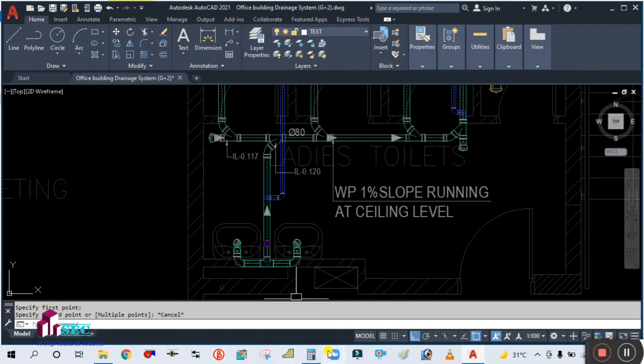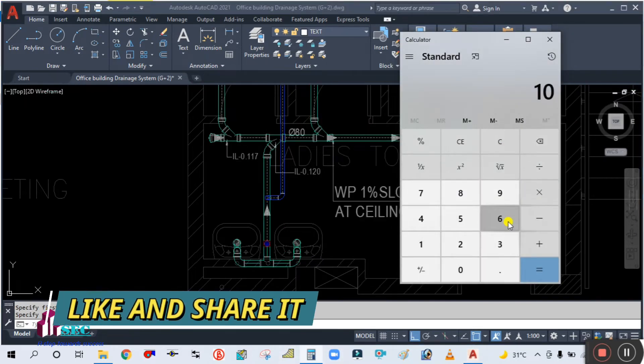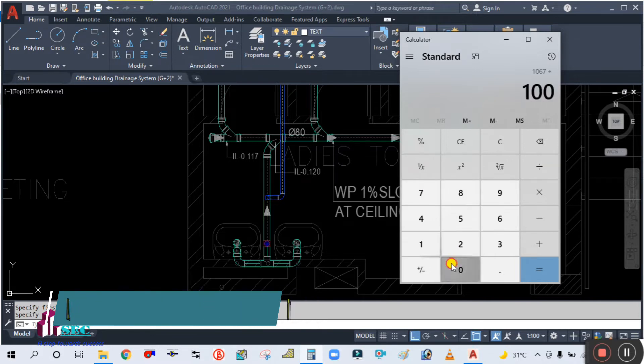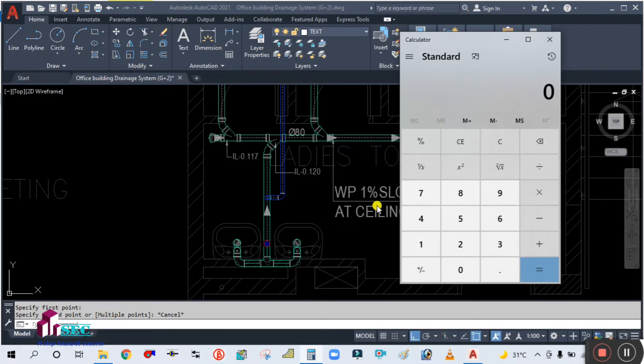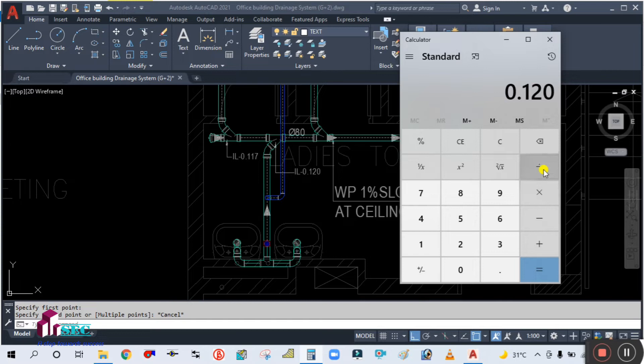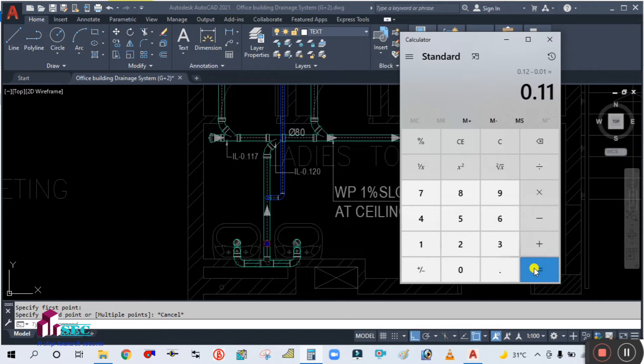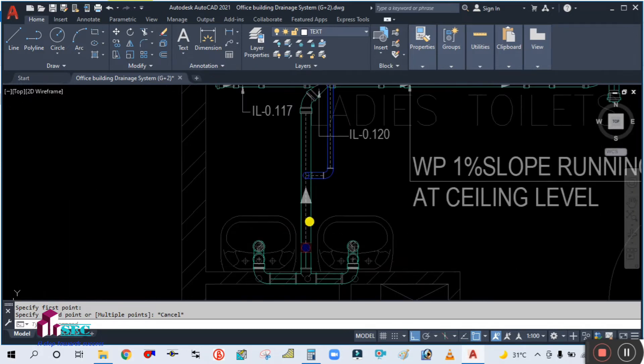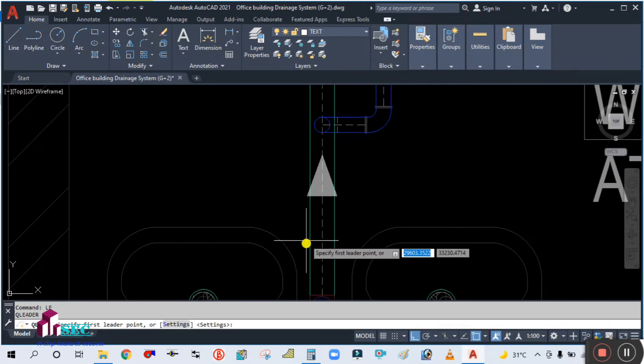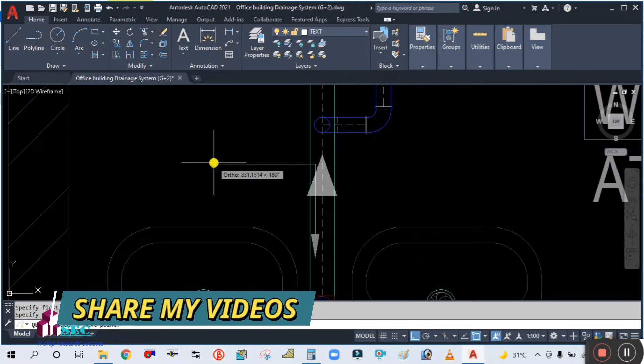The distance is 1067 mm. So 1067 divided by 1000, then divided by 100, gives 0.010. Remember this value — 0.010 should be subtracted from 0.120. So 0.120 minus 0.010 equals 0.11. Here your invert level will be 0.11.